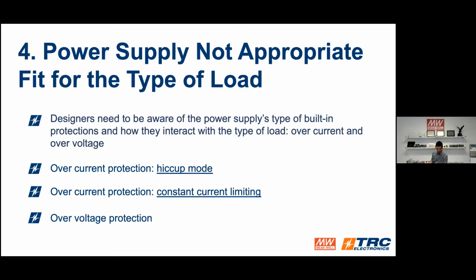Just like overcurrent protection, most power supplies come designed with overvoltage protection. Two main things: one, in case there's a defective component inside the power supply, the output voltage may rise above what it's supposed to be regulated to, which could damage the end device. With overvoltage protection, it's going to clamp—for example, a 24-volt supply may clamp to 30 volts to limit the damage. That's the purpose of integrating overvoltage protection into the power supply.